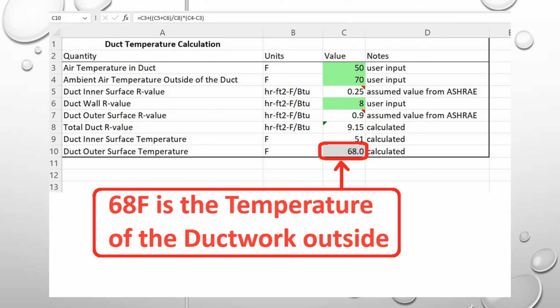All right, so I actually pulled this spreadsheet, or this formula, from the Trane Comfort site, which all our dealers have access to. If you're a Trane dealer, you have access to this. You plug in some numbers here. The air temperature in the ductwork is 50 degrees Fahrenheit, so that's our supply air temp. Then our ambient air temperature, which is our crawl space temperature, is 70 degrees. We all decided that as well.